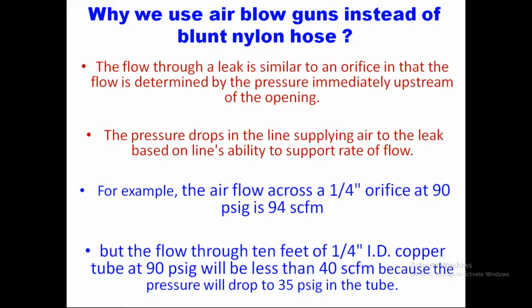You will be running a 20 HP compressor only for cleaning of a machine. Instead, you go for this transvector nozzle, and straight away from 100 CFM, or 94 CFM, you can bring it to almost 60 CFM only being consumed. 40 CFM you can save. This is what the energy savings is possible in the application of compressed air.